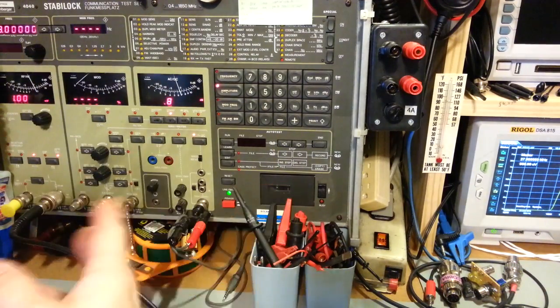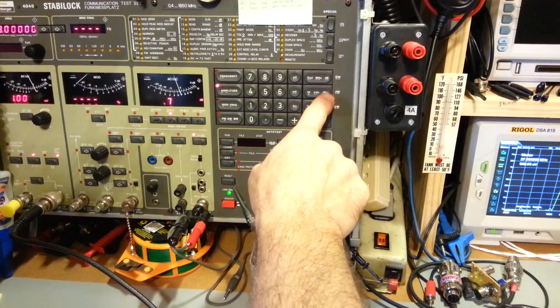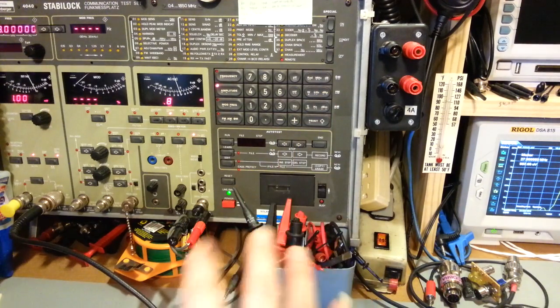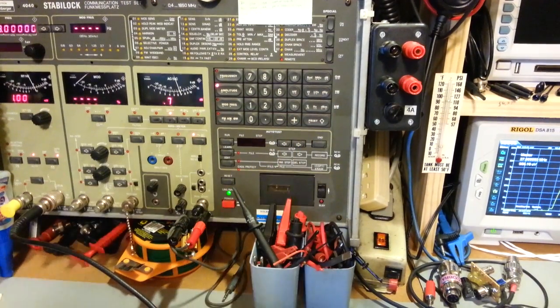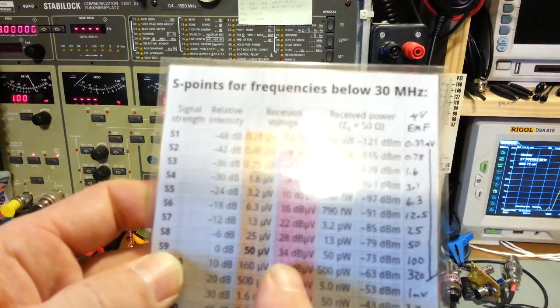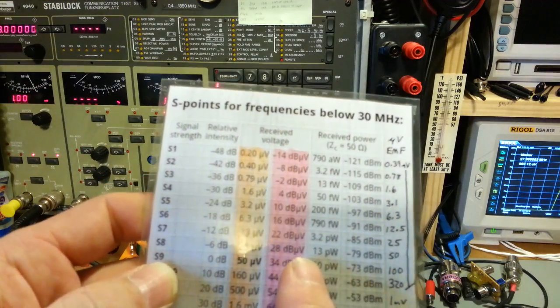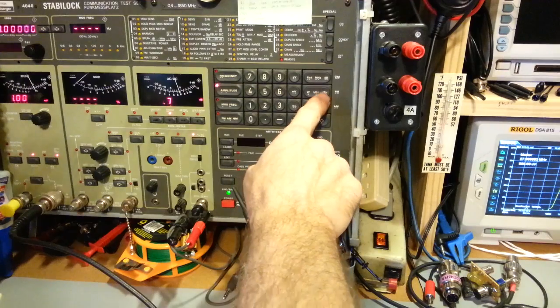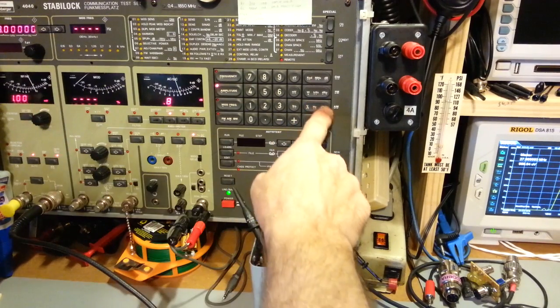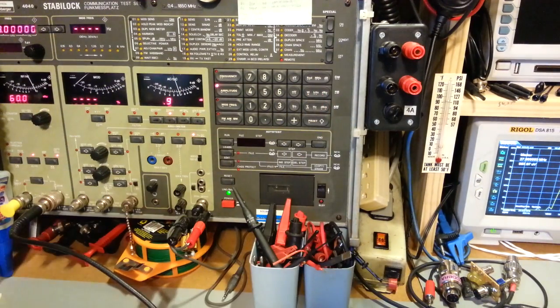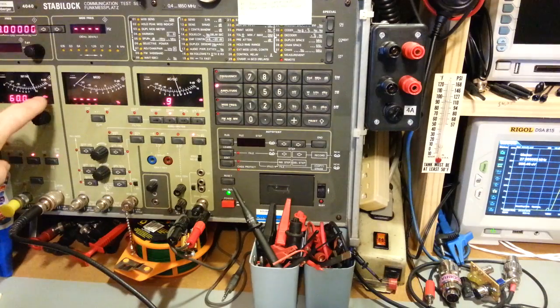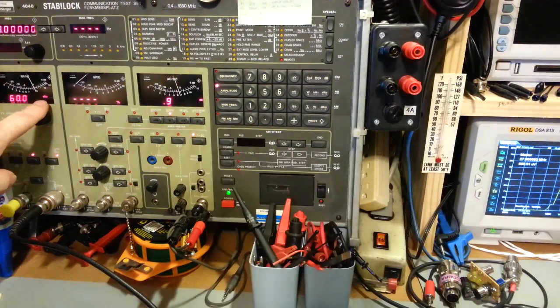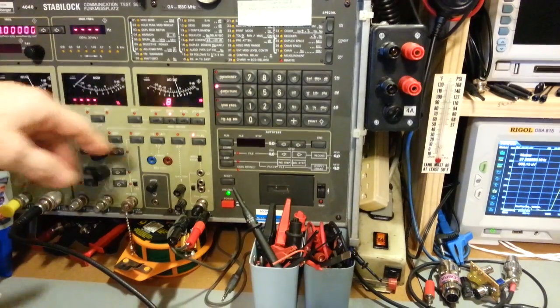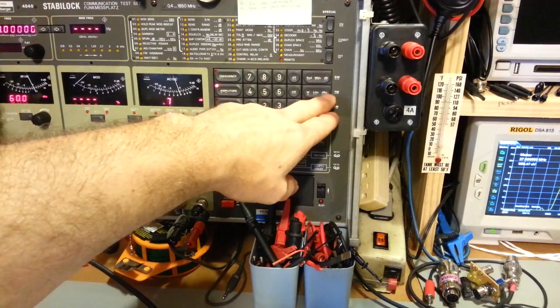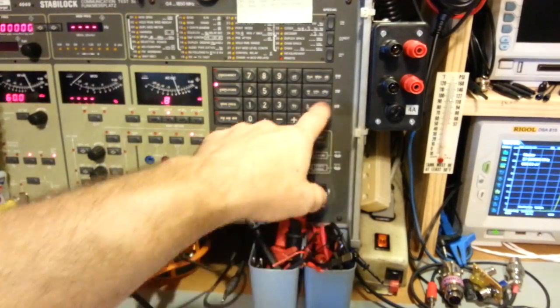so like I say, this will measure in microvolts, millivolts, any of the voltage measurements, but I can also do dBu, which you can find written in two ways. If you look at this chart, it's actually dBuV. So I can switch that. If you watch the meter over here, you'll see that change. So if I switch to dBu, so that's dBuV actually. Basically the same thing here. They just don't use the V. A lot of standards, a lot of times you'll see that the voltage or the V will be missing.